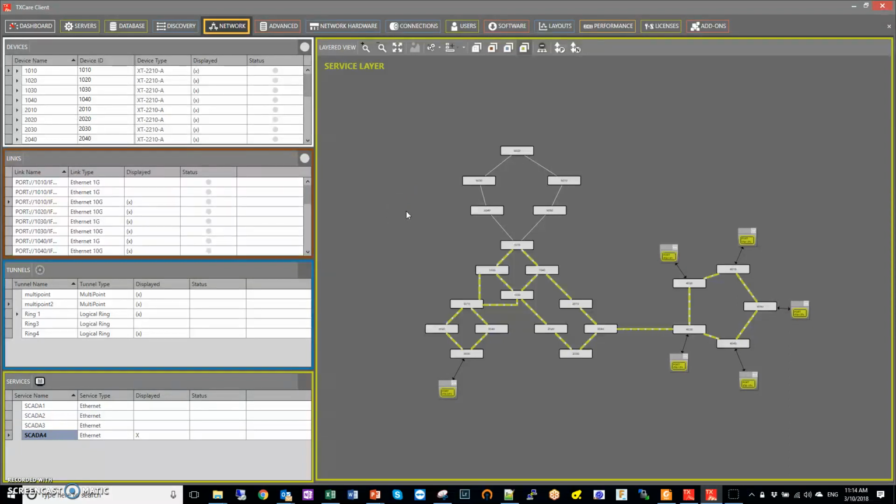One thing I cannot do is make a ring here, let's say ring 5. I can make a ring 5, but that ring cannot be a sub-ring of this main ring number 1 right here. And again, the reason is because I don't have two nodes right there. If I had two nodes, it would be possible. For example, like it right here and right there. But in this case, I cannot do this.